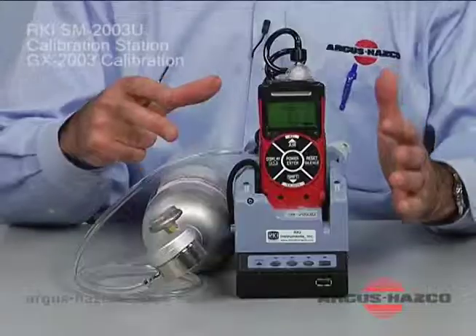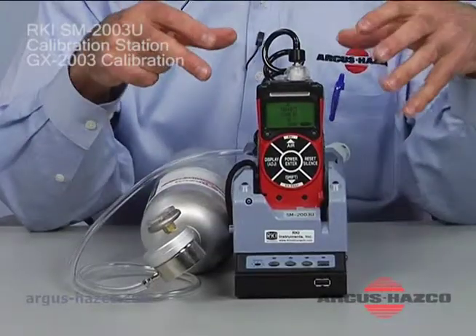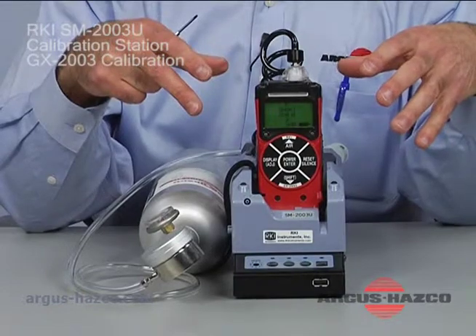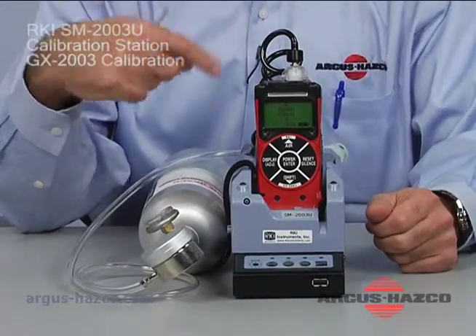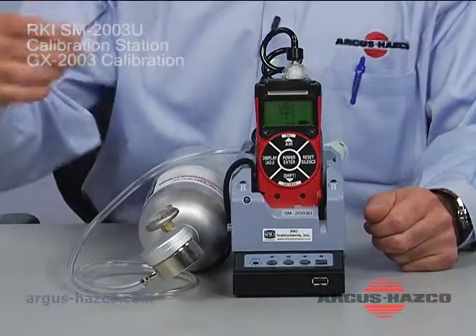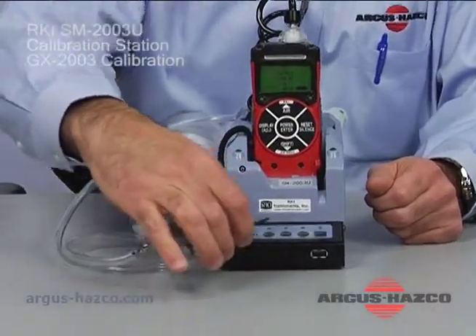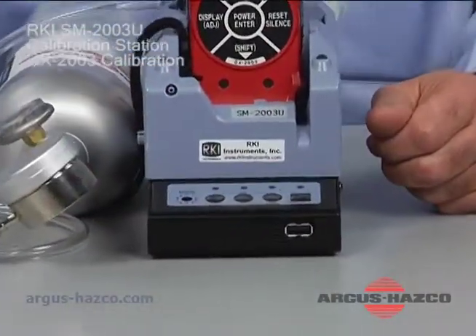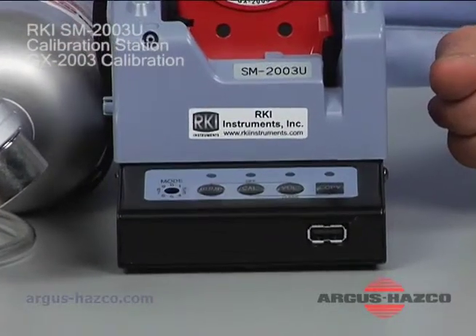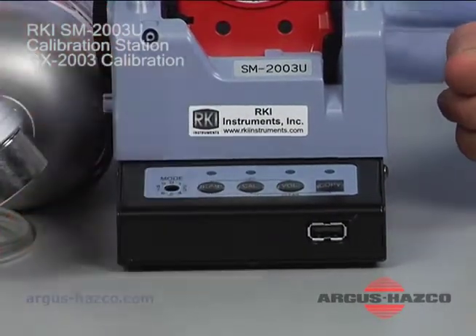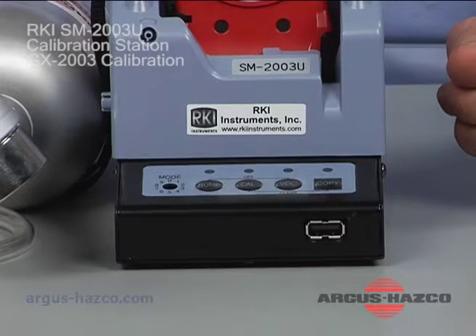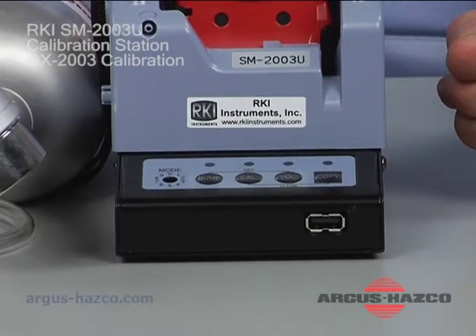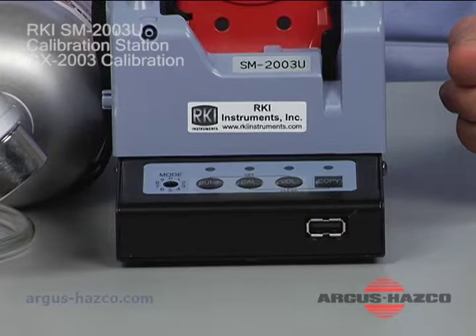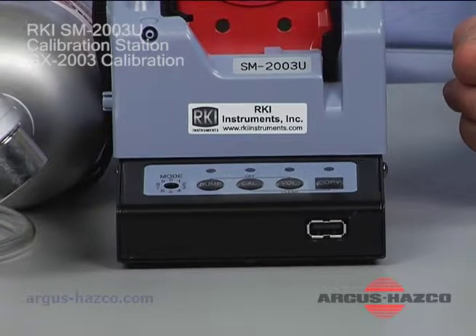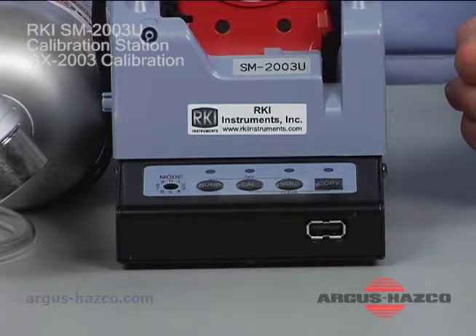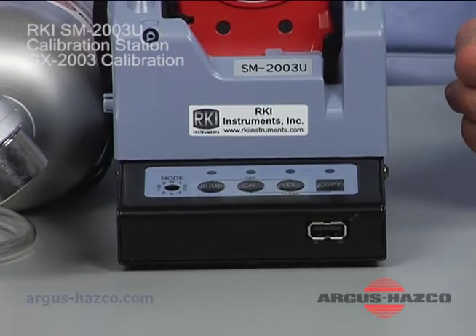Again, when we start to calibrate the instrument, we want to make sure the instrument's installed with it off, and then we turn the instrument on. It starts communicating with the cal station. And then what you see to the front end of the calibration station, you have several buttons. Okay? On the far left is a position switch. I suggest you turn that position switch to number 6. If you look on the manual to page 20, it will identify each position and what each position means.